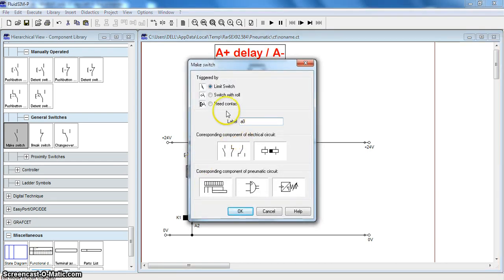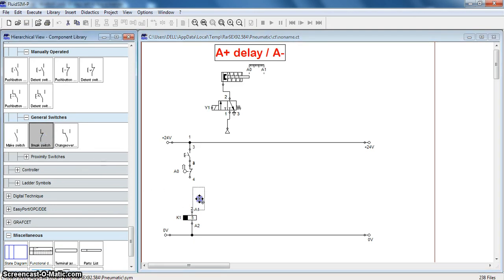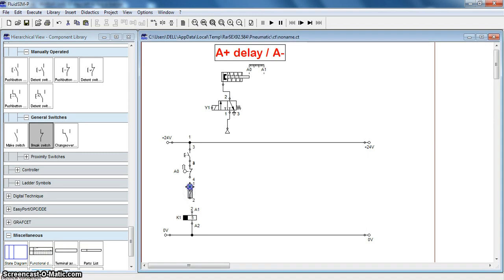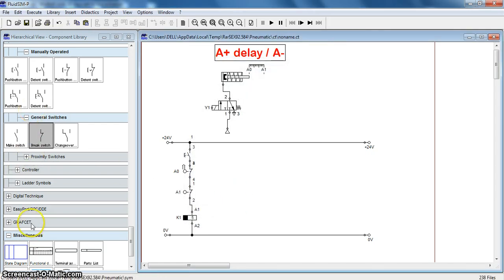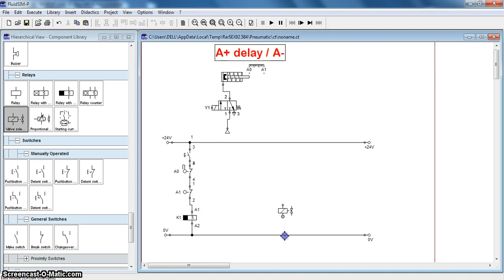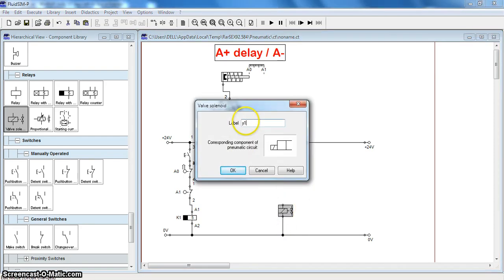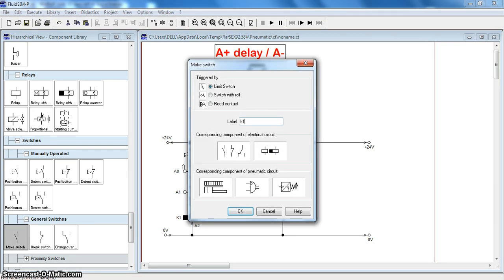This contact is A0 and it is a switch with a roll which is normally open. Since we want the next operation to start after the first operation happens, we will place here a normally close contact of A1. We can name this as A1 and it is also a switch with the roll. So we will place a solenoid valve here, connect it to the circuit, and name it as Y1. This will be activated by the make contact of K1, which is a limit switch.